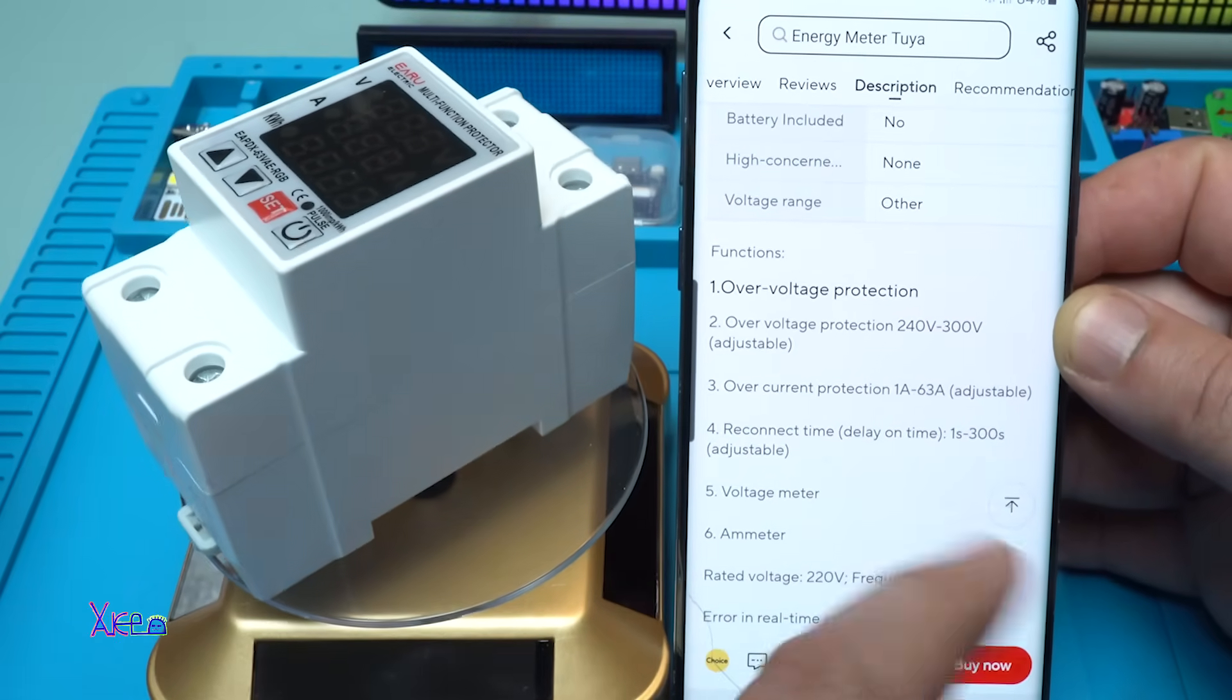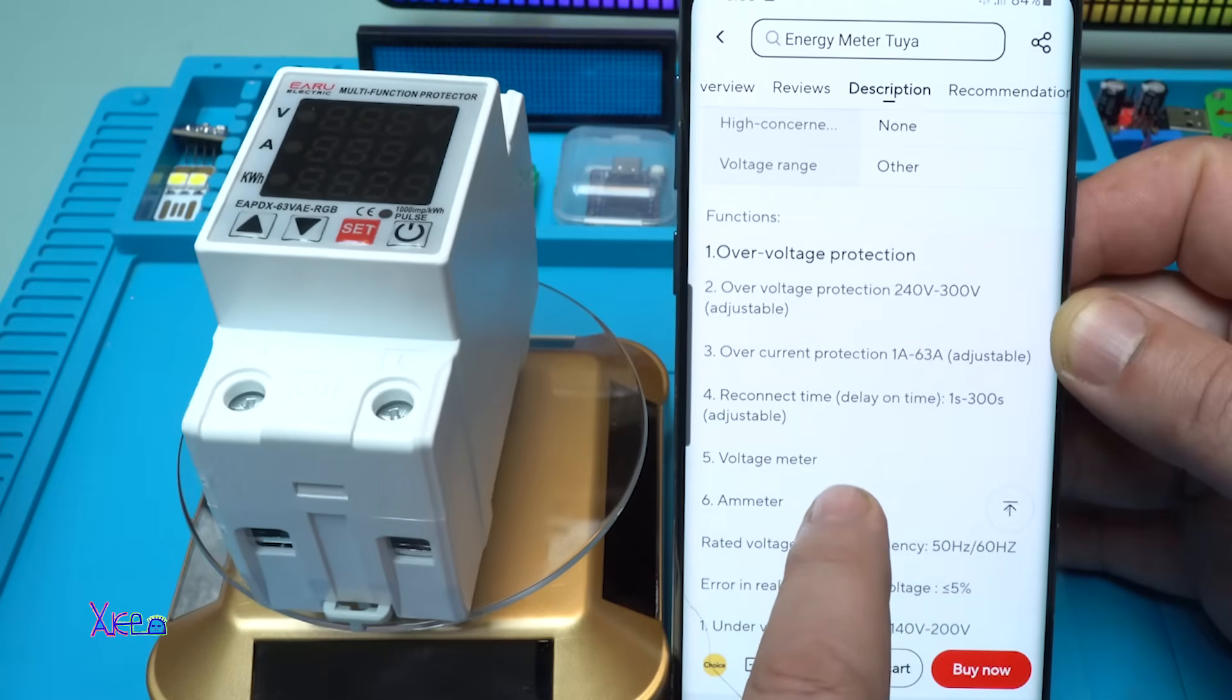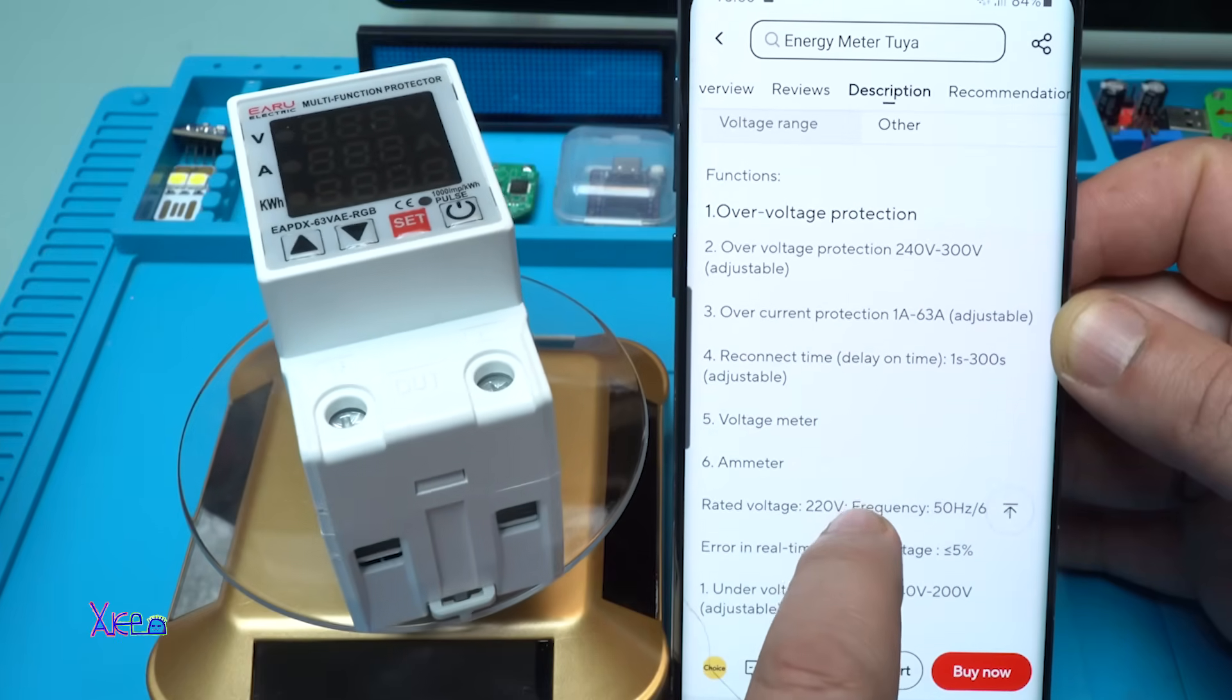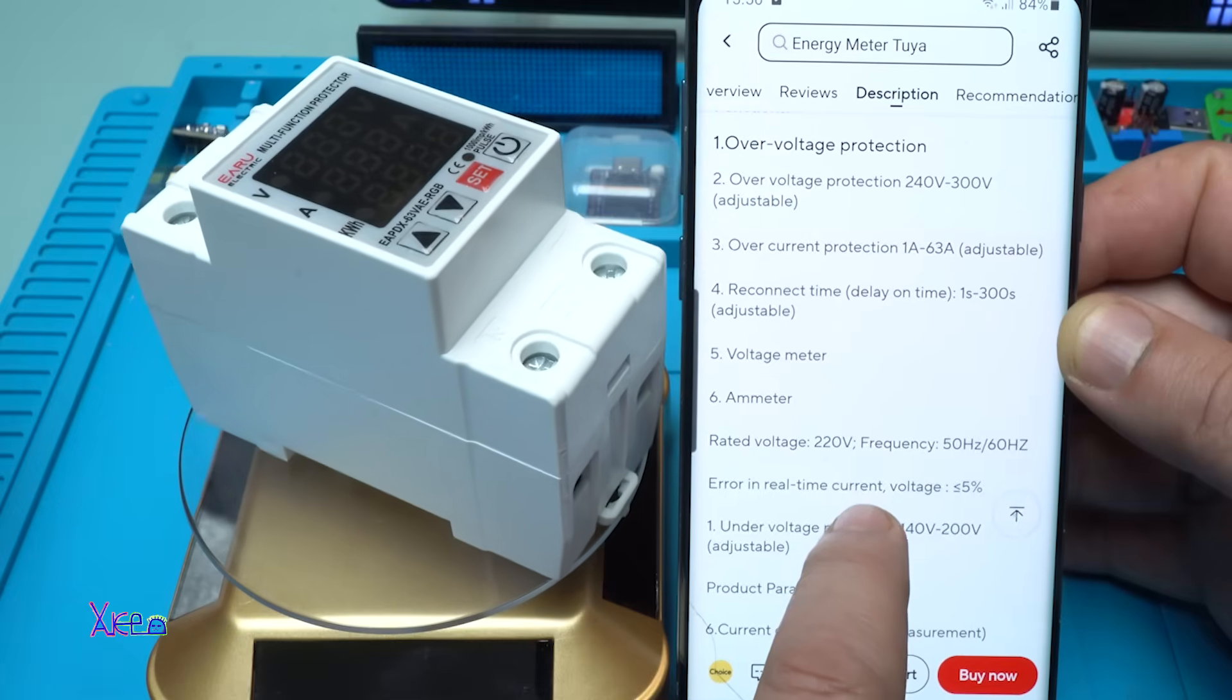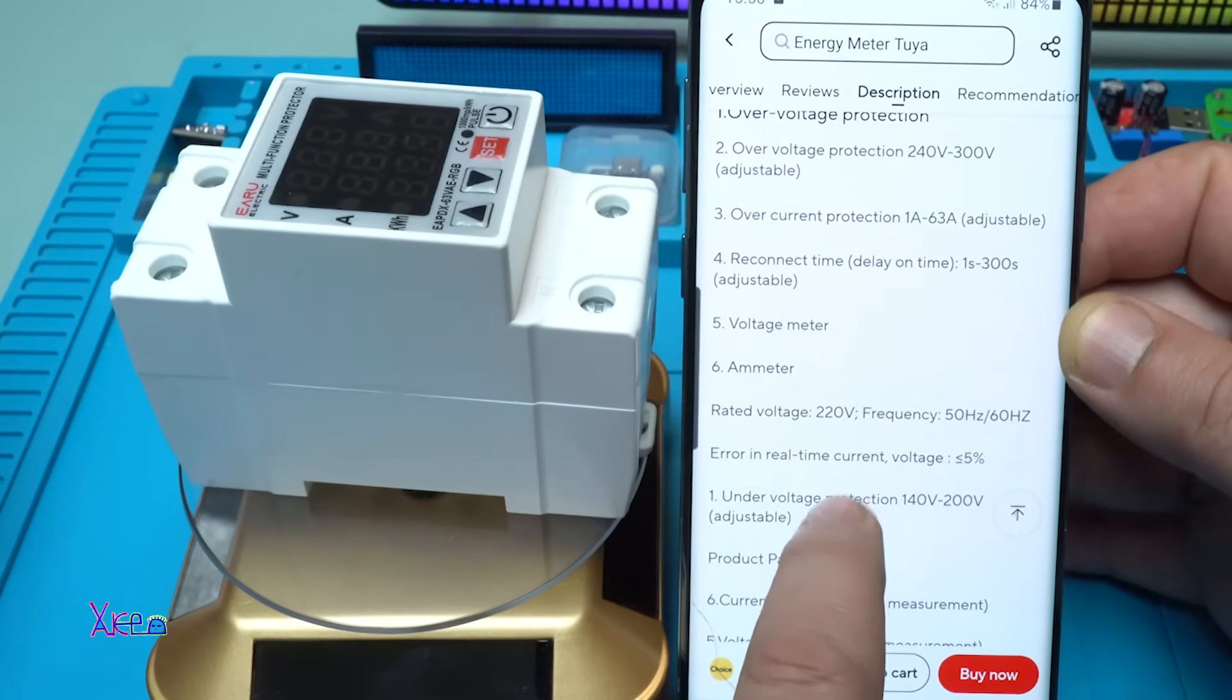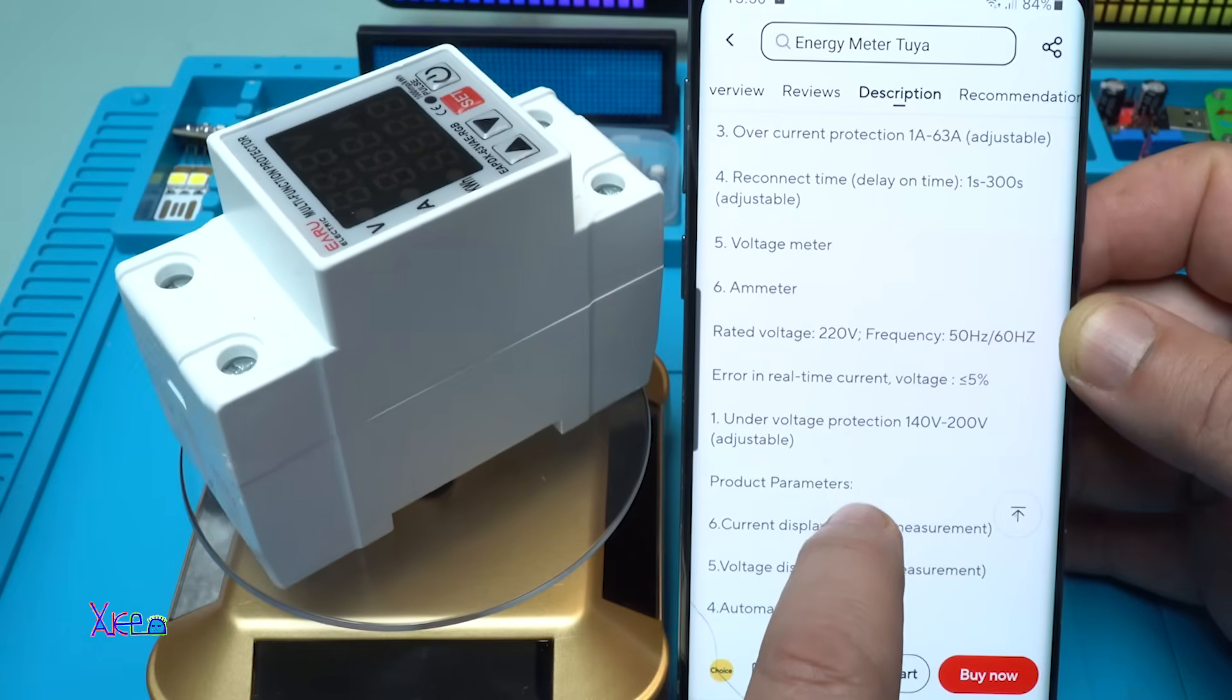Over voltage protection 240 to 300 volts, adjustable. Over current protection 1 to 63 amperes, delay on time, adjustable 1 second to 300 seconds, voltage meter, ammeter, rated voltage 220, frequency 50 or 60 hertz.